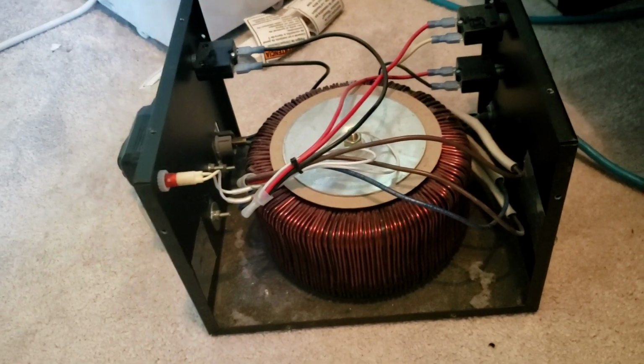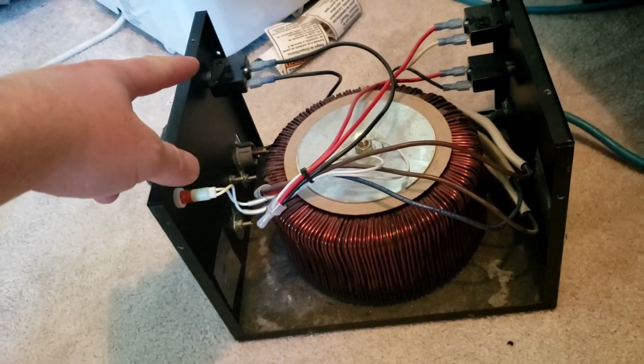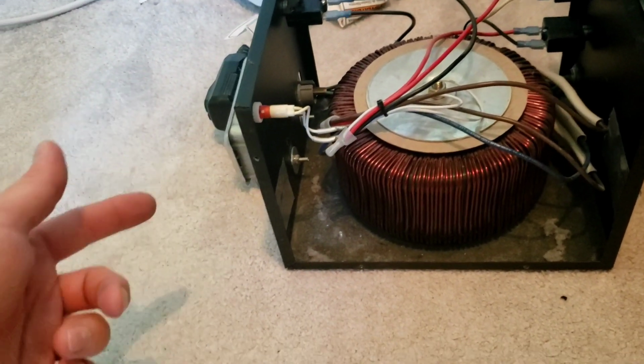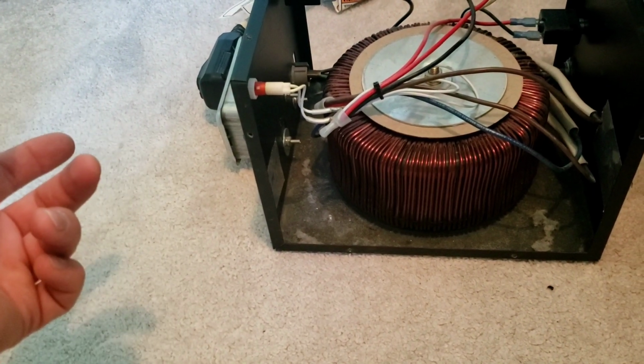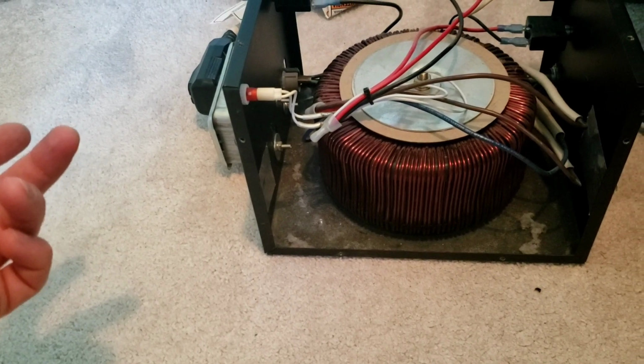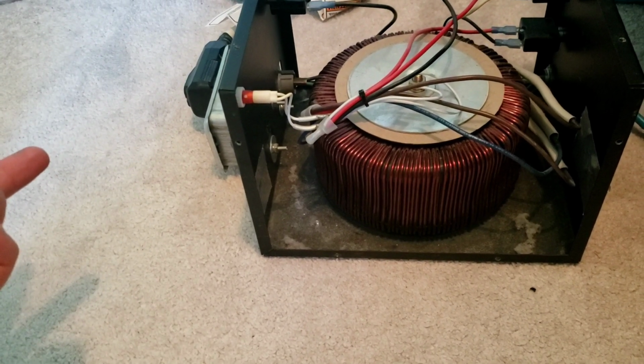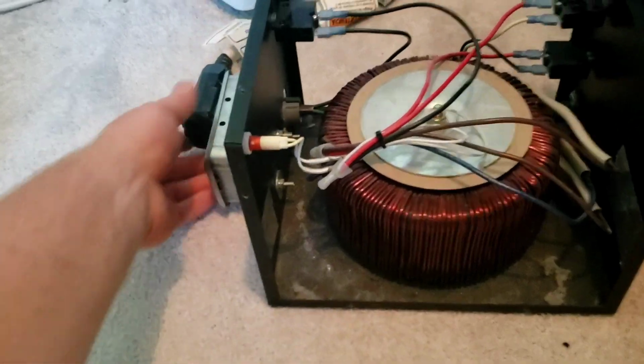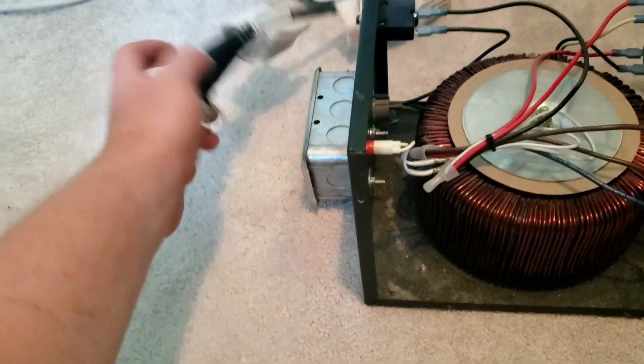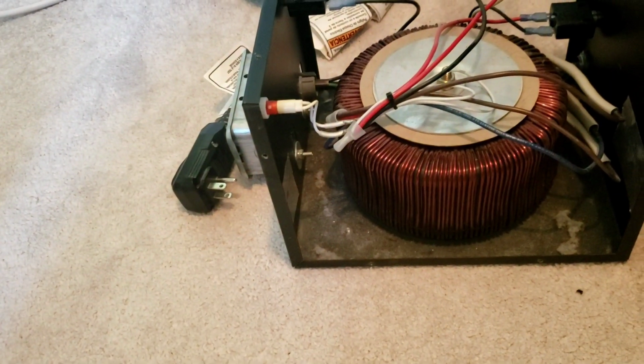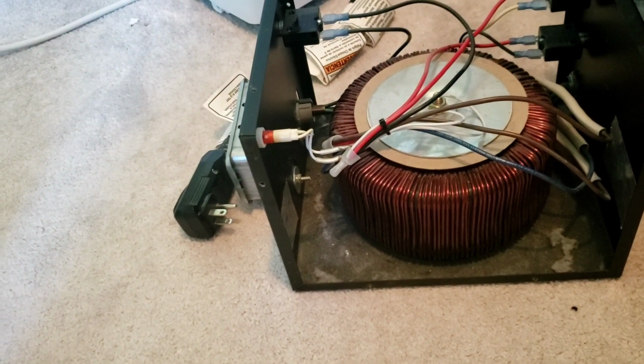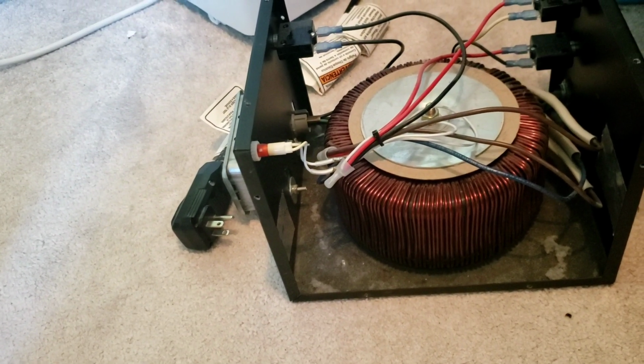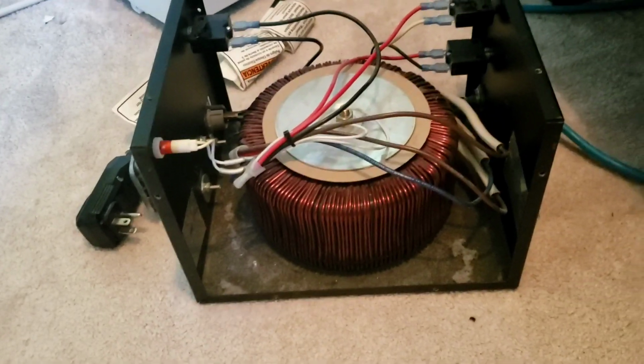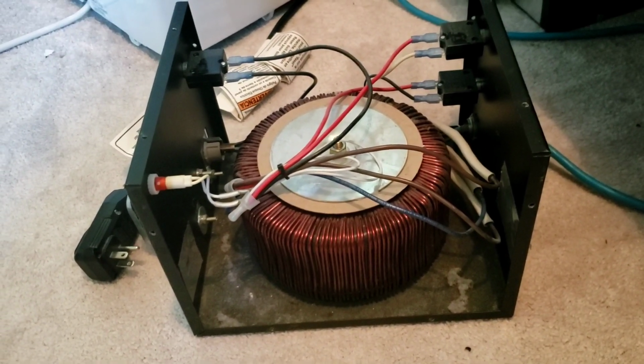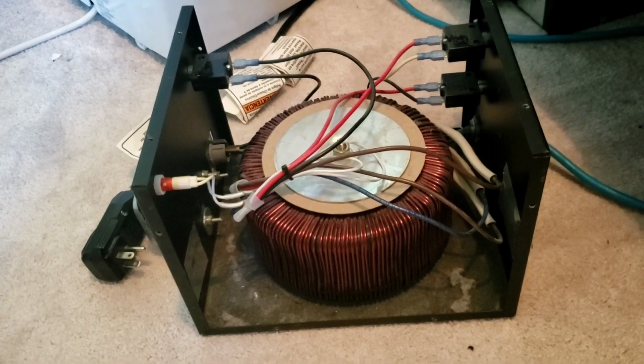This was all completely rewired, because this breaker was a 40 amp breaker protecting this weird receptacle I was talking about, maybe a 120/240 volt, 10 amp receptacle that can accept North American plugs as well as European plugs like behind that unit. That thing was terrible, protected by a 40 amp breaker, and the wiring was flimsy and poorly soldered, so I just ripped it all out, cut it off, scrapped it, and rewired it.